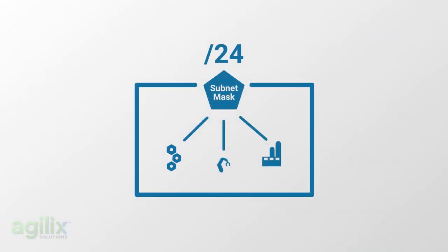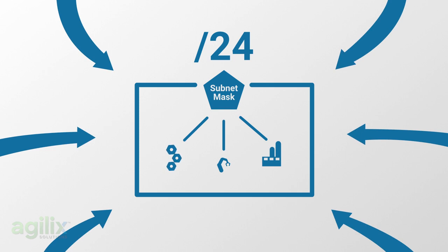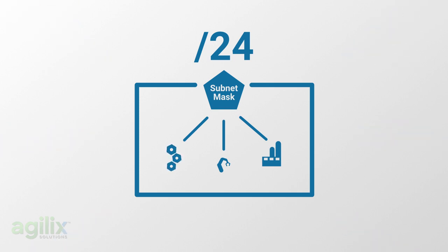If I stay consistent with the /24 across my industrial process, it's very easy to identify whether it's been correctly configured or not. Picking a smaller subnet mask, /24, keeps the noise out of the process of other devices communicating, which can affect our communication within that process, and will allow us to quickly determine and quickly isolate why the communications is not occurring.